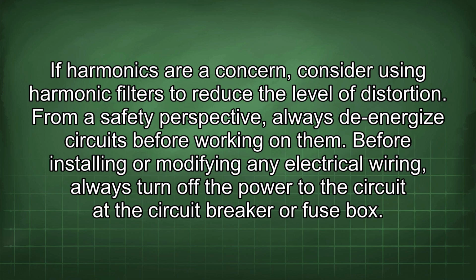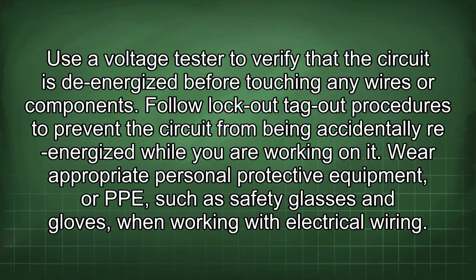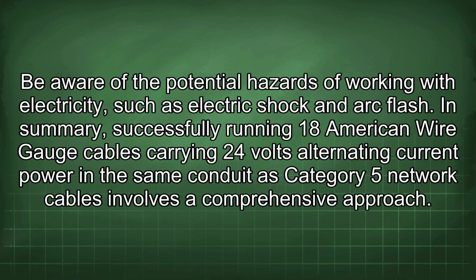From a safety perspective, always de-energize circuits before working on them. Before installing or modifying any electrical wiring, always turn off the power to the circuit at the circuit breaker or fuse box. Use a voltage tester to verify that the circuit is de-energized before touching any wires or components. Follow lockout-tagout procedures to prevent the circuit from being accidentally re-energized while you are working on it. Wear appropriate personal protective equipment, or PPE, such as safety glasses and gloves when working with electrical wiring. Be aware of the potential hazards of working with electricity, such as electric shock and arc flash.